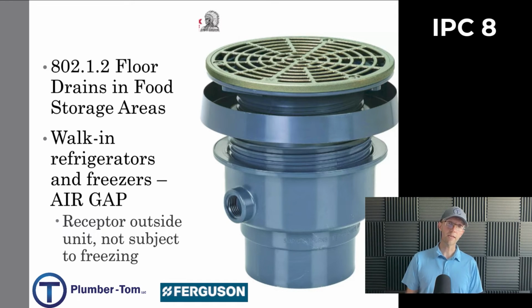And it's very important that that does not get clogged or frozen, right? So if you have a condensate drain and it's moving through that freezer, but the floor drain is in the freezer, then it's going to freeze up. It's going to cause big problems with that refrigeration unit. So specifically, the receptor has to be outside the unit and not subject to freezing.